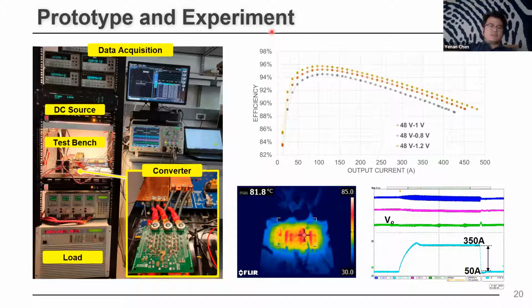This is our test bench and prototype of the 48 volt to 1 volt CPU voltage regulator. You can see several capacitors and switches on top of the circuit board. This is the test system with a data collection setup, where we collect input power and output power to calculate efficiency. This is the input source providing 48 volts, the converter, the cooling fan, and we use two high current loads to consume the high output current.